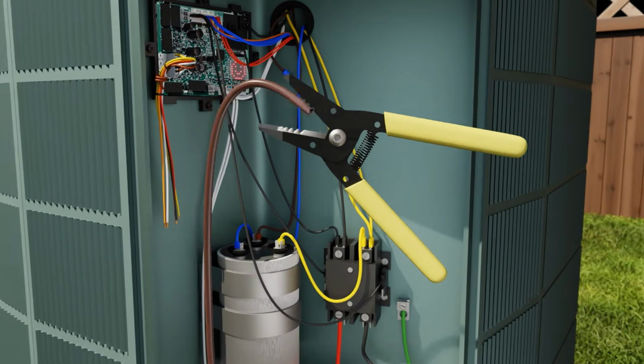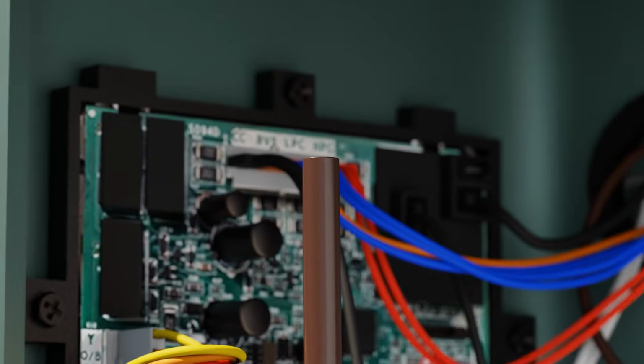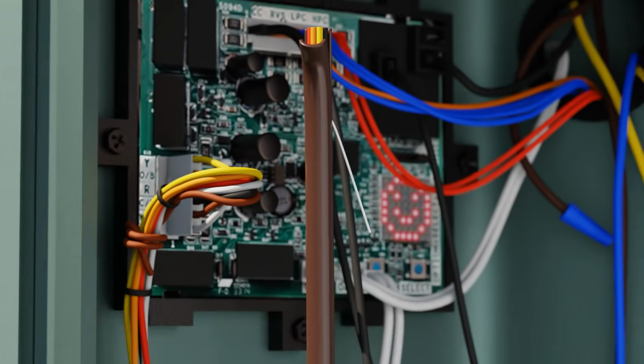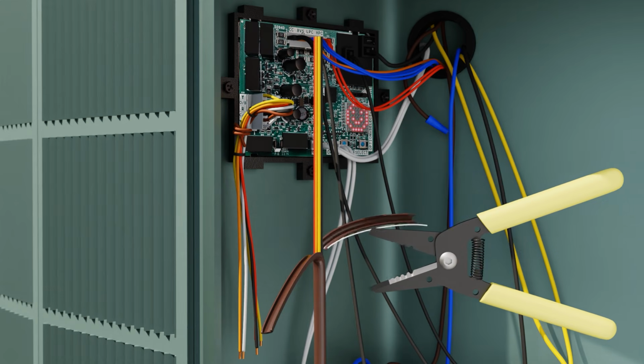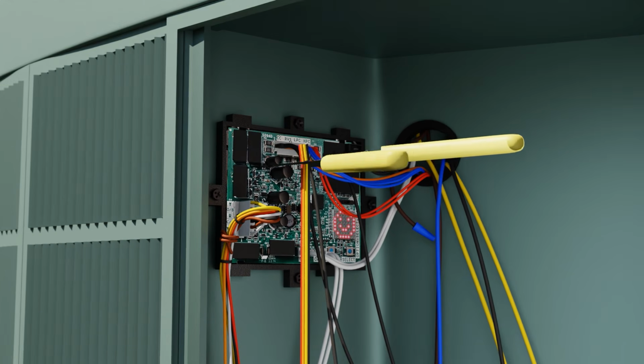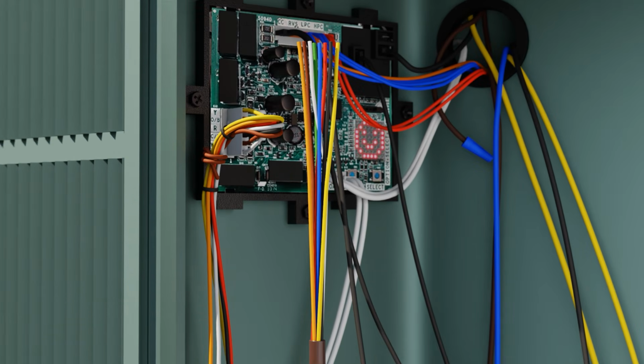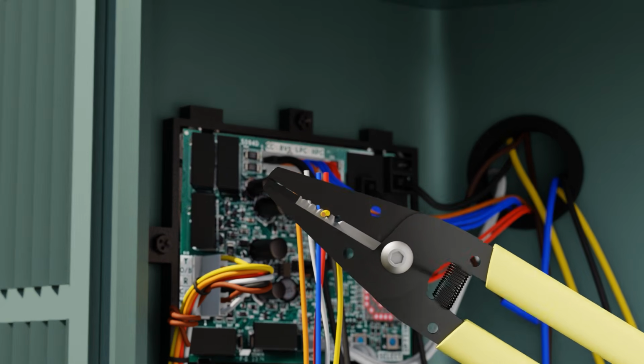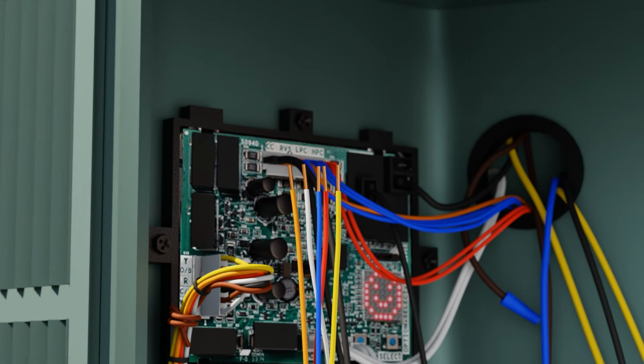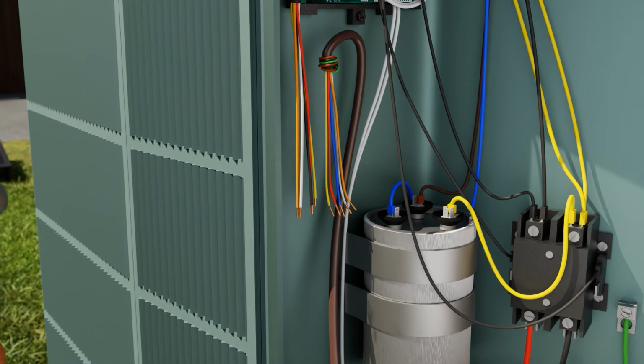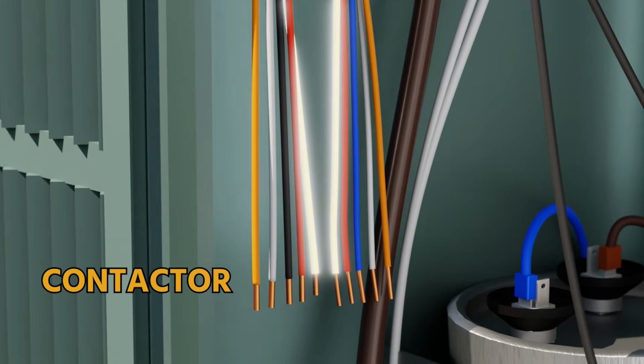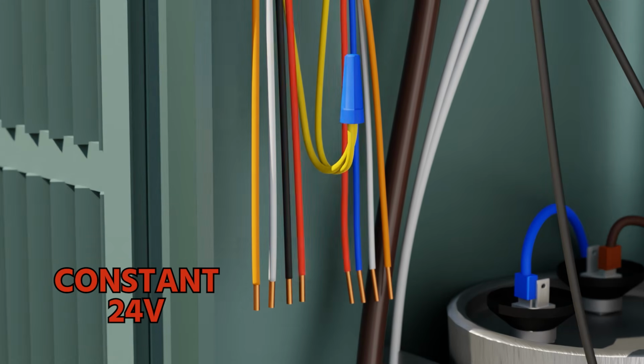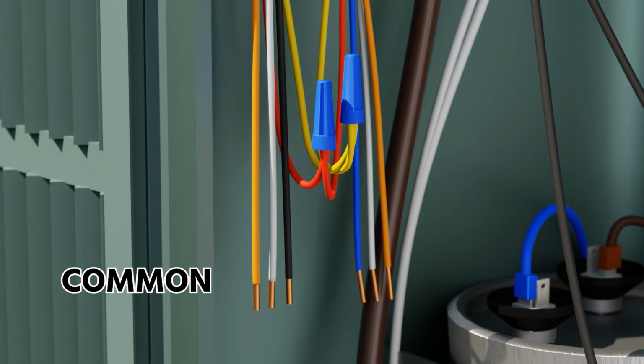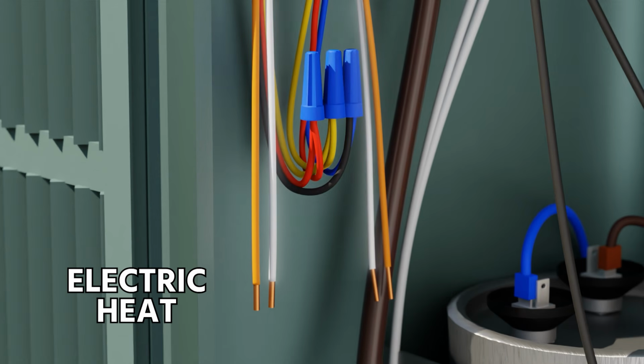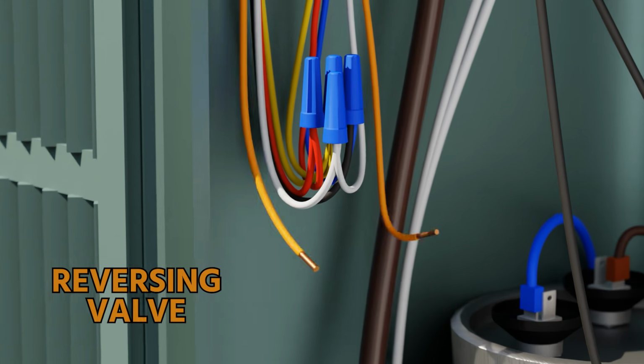Snip into the end of the wire and peel back the jacket using the string or one of the unused conductor colors. Then you cut the jacket off and snip off the wiring portion you cut into initially. This ensures that you don't have any nicks in your wires. When stripping back the insulation from each conductor, only do it as long as you need to make a good connection. You don't want to leave any bare wire left over. Next, you connect each conductor one at a time. Yellow for your contactor, red for constant 24 volts, black because that's the color Carrier uses for common, white for your electric heat, and orange for your reversing valve.